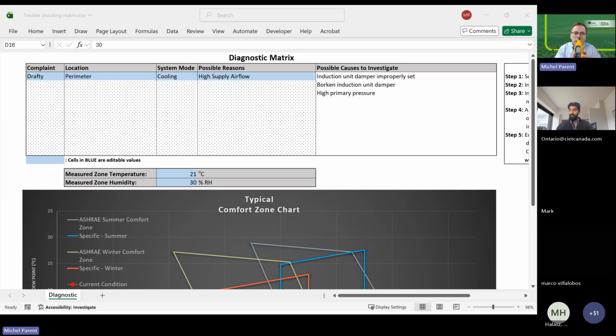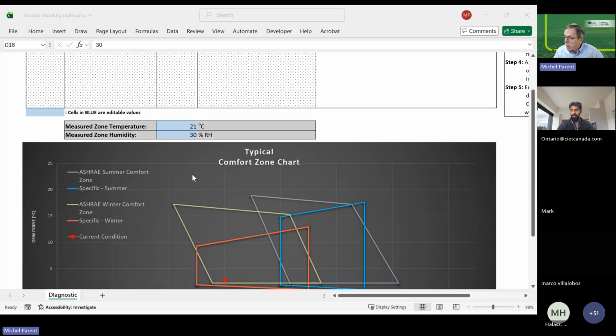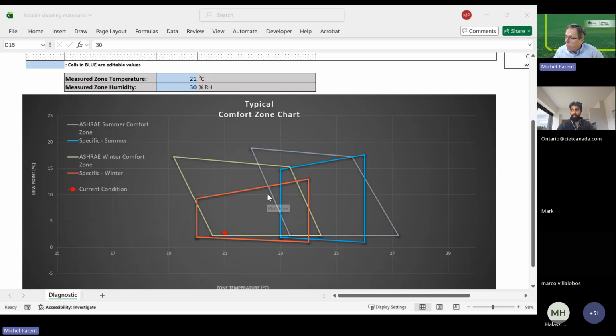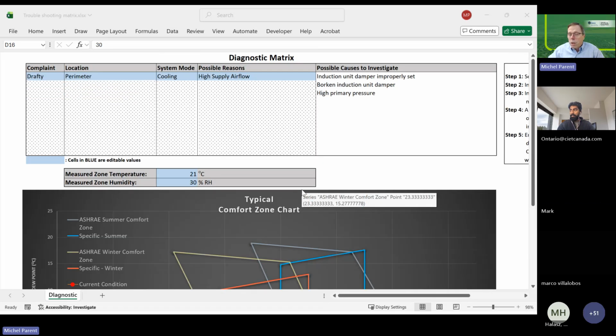You need to use something like this. It has a thermistor and it will measure temperature and humidity. Do that. Make sure your operators know that they have to use something like that. You enter the humidity and the temperature. It will tell you, am I in the comfort zone of my building? The red box is the heating comfort zone that you can actually customize to your building. And well, this tool was developed for a VAV system serving the interior of a building and an induction system serving the perimeter. I did not have time to generalize it to all kinds of systems.